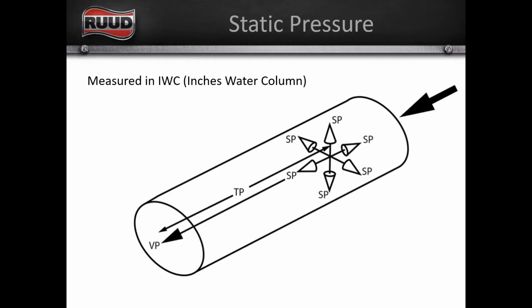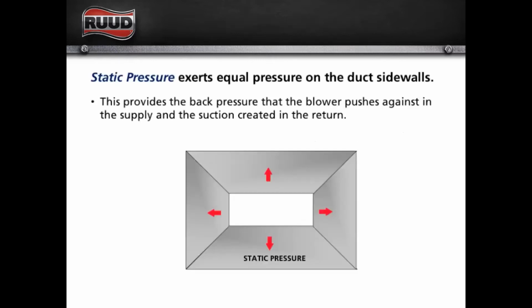There are a couple of other pressures that we can measure in the air. There is the velocity pressure, which is really just the speed of the air moving through the duct. And then there's the total pressure, which is we just add the velocity pressure and the static pressure. For our purposes, we're much more concerned with static than with velocity and total pressure when it comes to making sure that we're moving the right amount of air. And when we start looking at blower tables, you'll see that that's all driven by the static pressure. Again, the static pressure is the pressure being applied or pushed on the sidewall of the duct, on the inside of our duct.